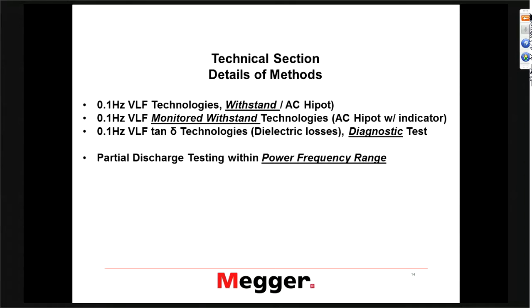This is actually written up and described in IEEE 400.2. Compared to just a plain hipot test, a monitored hipot test offers good additional information, which is why I think a monitored hipot test is always to be preferred over a plain hipot test.